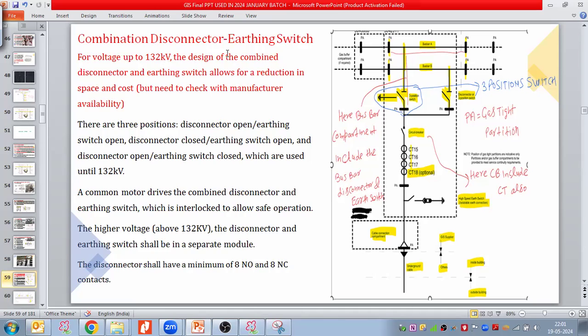Up to 132 kV, the design of the combined disconnector and earthing switch allows for a reduction in space, and it also provides a reduction in the overall cost. It means we take a 3-position disconnector switch. So there are 3 positions. This is how the statement is converted into the drawing. Here we have bus bar A, and from the bus bar we take this disconnector, and this disconnector is combining the earthing switch module in one.